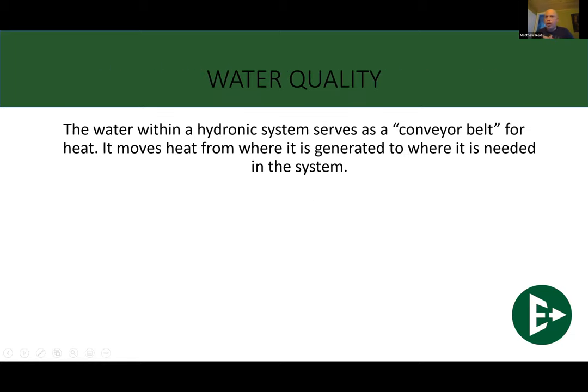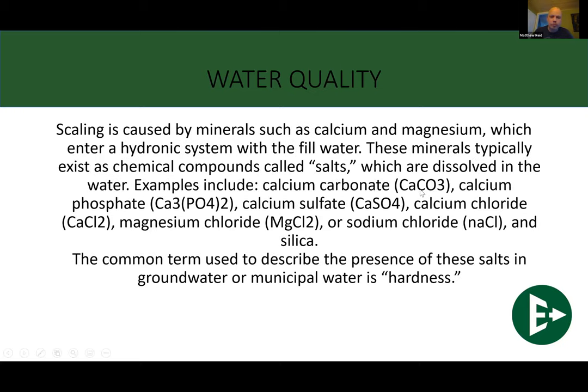All right. We're getting into water quality. We've got about half an hour left, which is good because that's the time we've got. When we think about water inside of a hydronic system, think of water like a conveyor belt. It delivers heat to an area, and then the water comes back, picks up more heat from the boiler, takes it back out, and delivers it to an area. That's how water works inside of a hydronic system. Now, this slide is going to look terrifying because of all the CaCO3 and PO4, but this is what I'm going to be getting at here. Remember our conveyor belt.